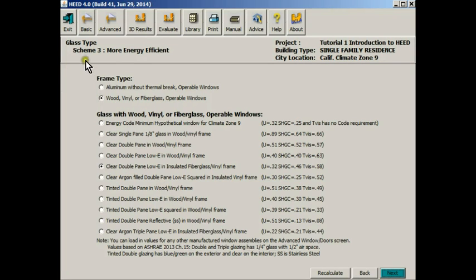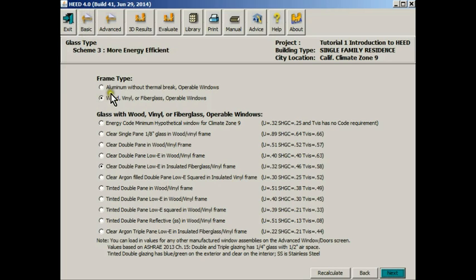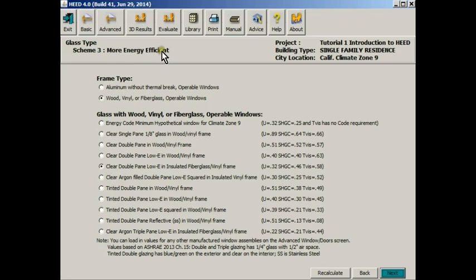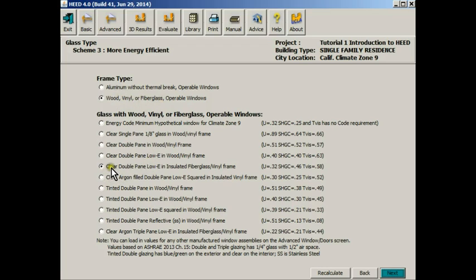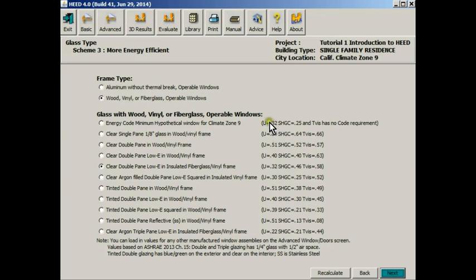In HEED all the basic design elements are defined in lists such as this. The user can pick off what they choose. In this case for the more energy efficient building, HEED has selected wood frame or fiberglass windows. Here the window that he chose is clear double pane low-E with an insulated fiberglass frame. It has the same U value as the code compliant window, which is the energy code minimum window, but it allows for more solar heat gain. So in this case it's a much better passive solar window.